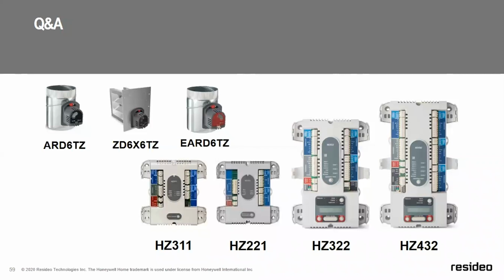If you have trouble where you're going back and forth and you cannot get them to balance, you've either sized your bypass too small, or there is an issue with your ductwork downstream from the zone system. In which case, really, you're going to have to either tweak your bleed throughs on your dampers, or decide if it's acceptable to bypass a little bit of air when all of your zones are calling, because really at that point you're trying to make the best of a bad situation, because a lot of times you can't really redo a customer's ductwork, so sometimes we just have to deal with stuff.